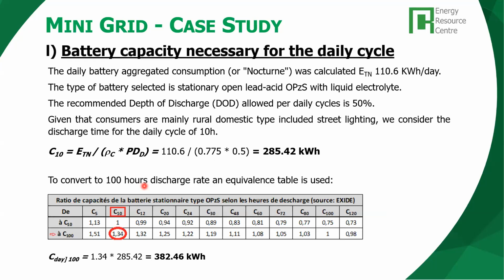Now the battery. Remember, for the battery, we have been looking at what fraction of the total consumption will be nocturnal. In this case study, we have an overall consumption of 132 kilowatt hour per day, but the night fraction is 110.6 kilowatt hour per day, roughly 111 kilowatt hour per day. Okay, the type of battery that we have considered for this project is the lead acid open type of batteries with liquid electrolyte.